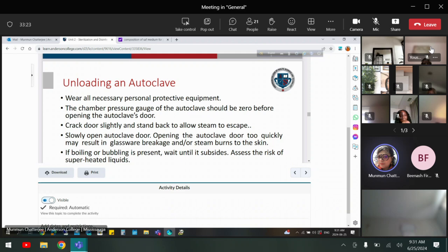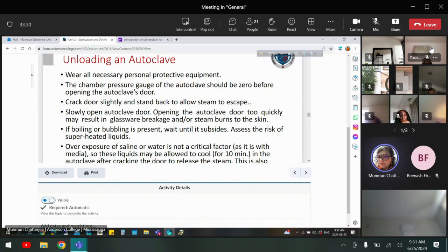Crack the door slightly and stand back to allow steam to escape. Slowly open the autoclave door. Very slowly you have to open it, even if you have done everything right, because you may still see some steam coming out. So stay a little bit back and open the door slowly. It is like whenever you cook: if you open the lid slowly when it is boiling, versus opening the cover immediately, with the latter suddenly the steam goes in your face. If you open the cover slowly, it mixes with the air and doesn't splash. Like a pressure cooker, an autoclave is just a pressure cooker.